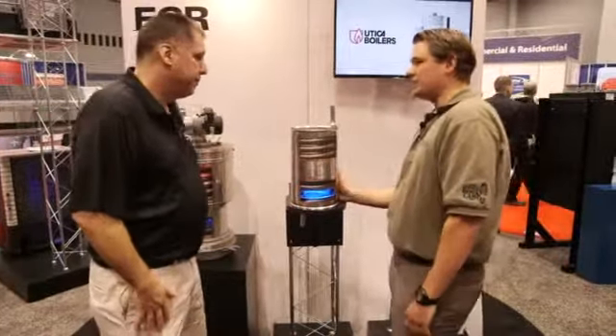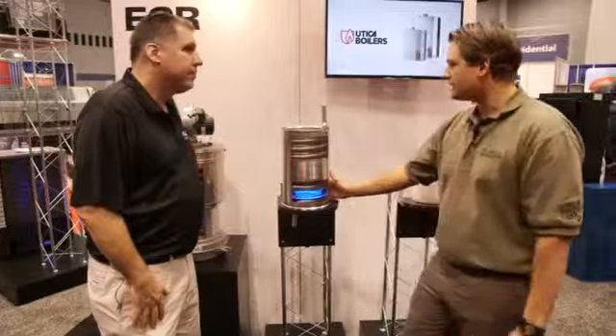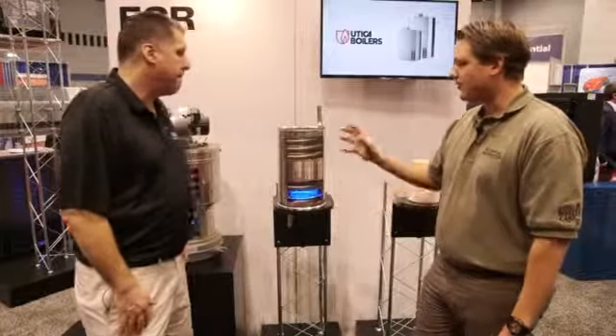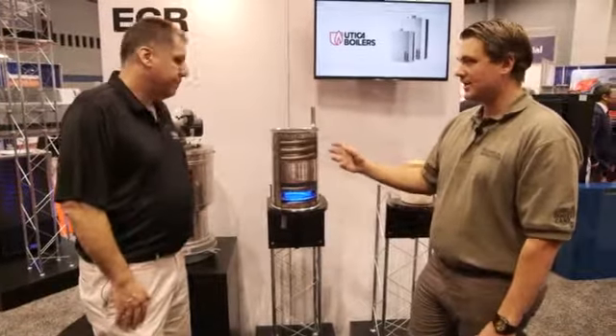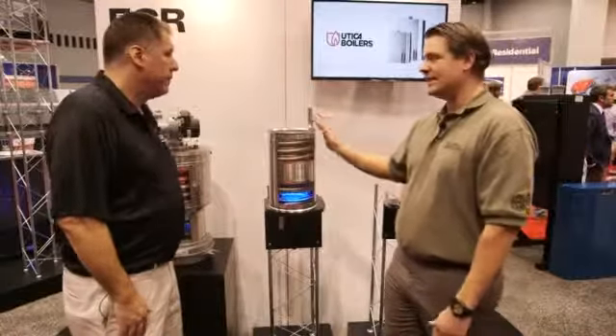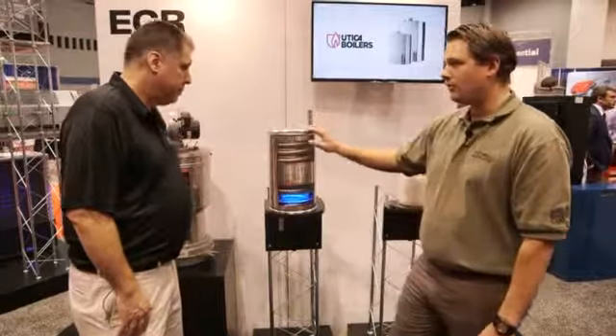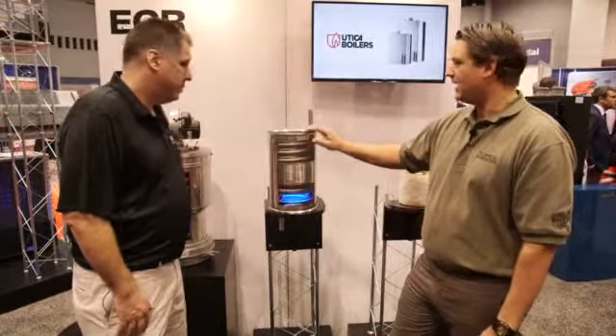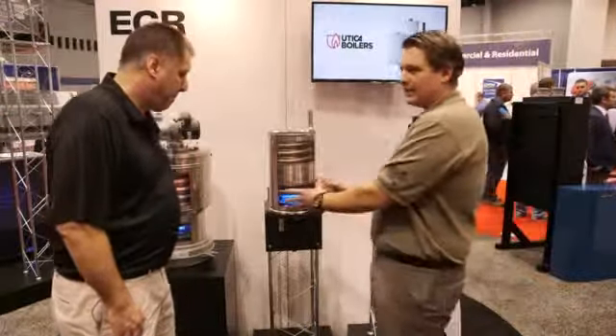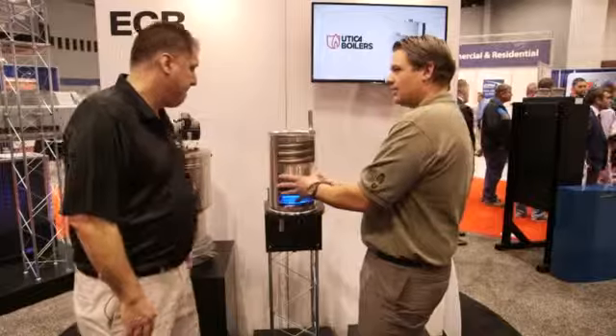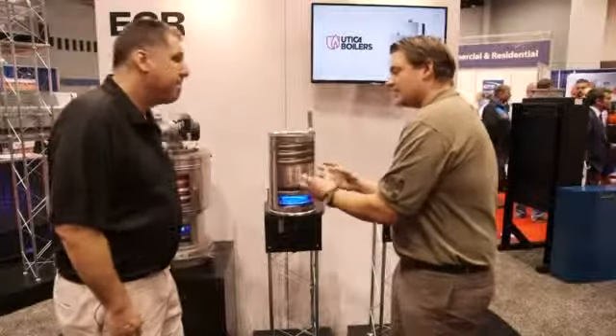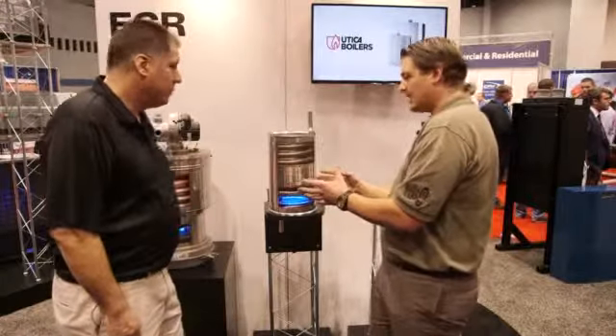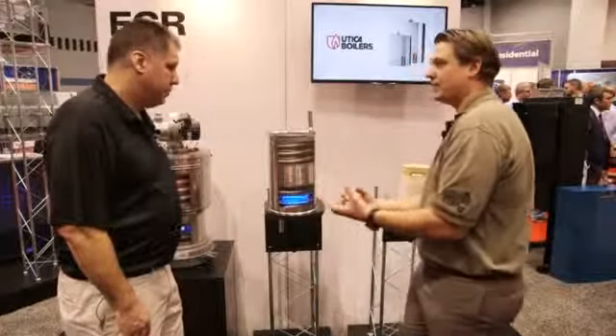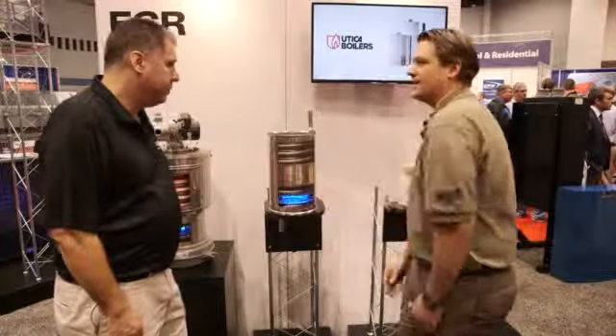This is our own heat exchanger design. It is owned by Utica Boilers, ECR International. It's a vertically mounted stainless steel heat exchanger. We got 316L on the tubes, 444 stainless steel fins on that, and it's a wide open passageway. Another unique feature, it is self-cleaning. Because it's horizontal, anything that builds up on there, when you have the expansion and contraction going on of the heating cycle, it's going to break off anything that's building up and then wash it down with the condensate.